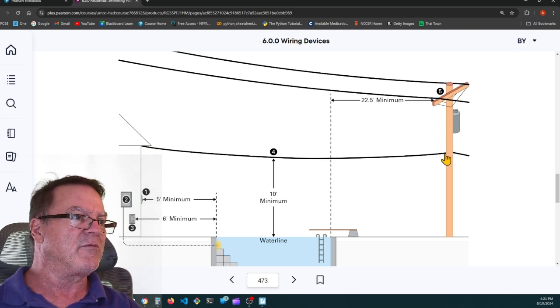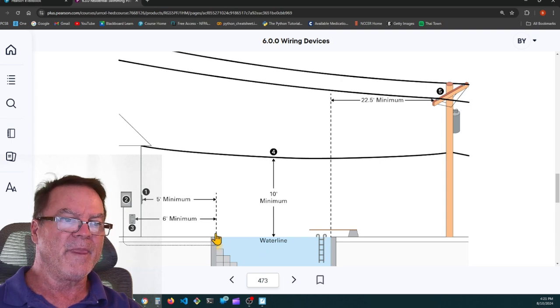This actually has to be a minimum of 10 feet above the high level water mark in the pool. And again, we have to be at least 6 feet away from the receptacle and 5 feet away from a switch on a wall on the house.